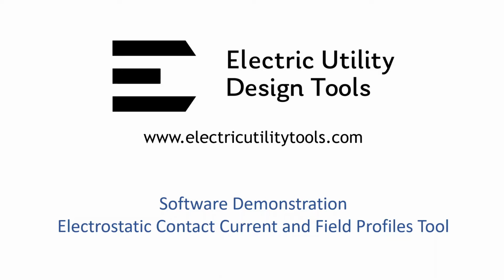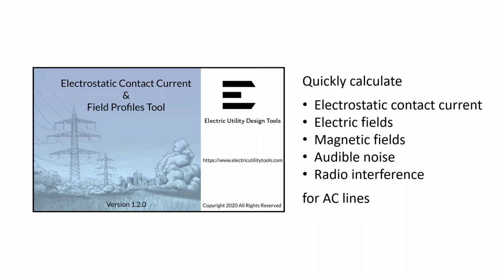This video is a demonstration of our electrostatic contact current and field profiles tool. The purpose of this software is to help engineers quickly calculate electrostatic contact currents, electric and magnetic fields, audible noise, and radio interference for overhead AC lines. I'll briefly explain electrostatic contact currents and then we'll jump into the demonstration.